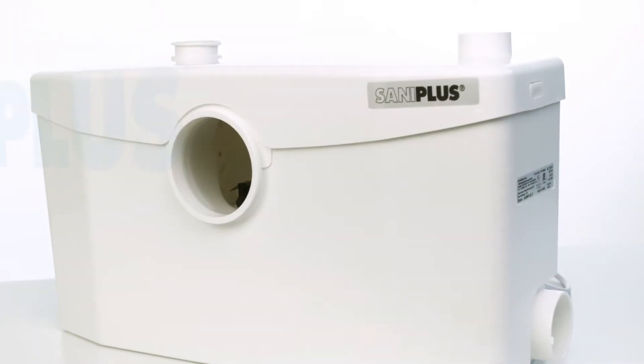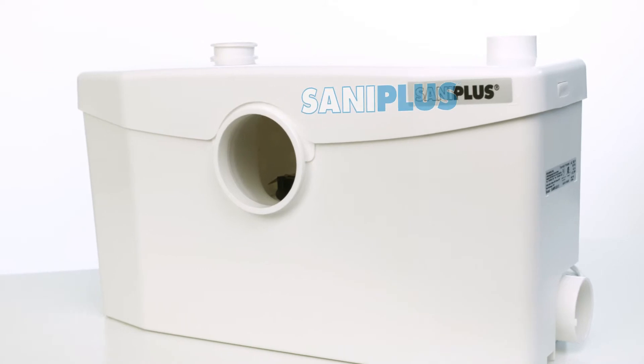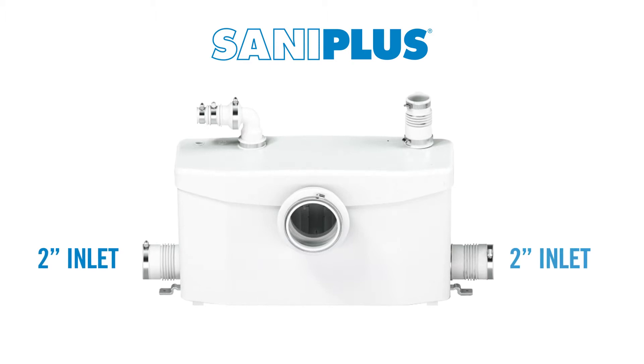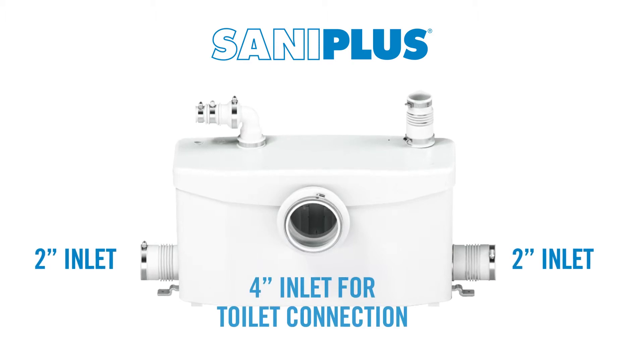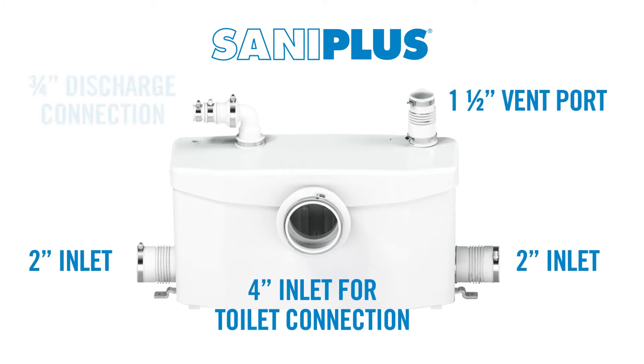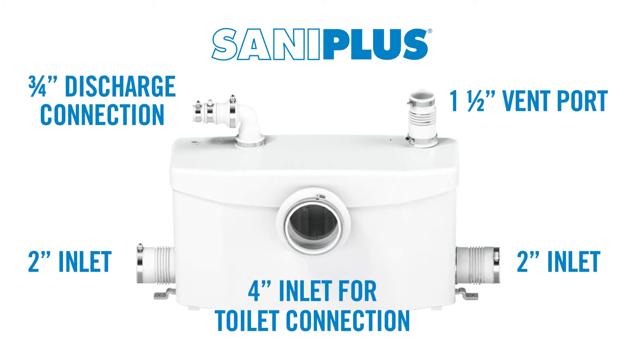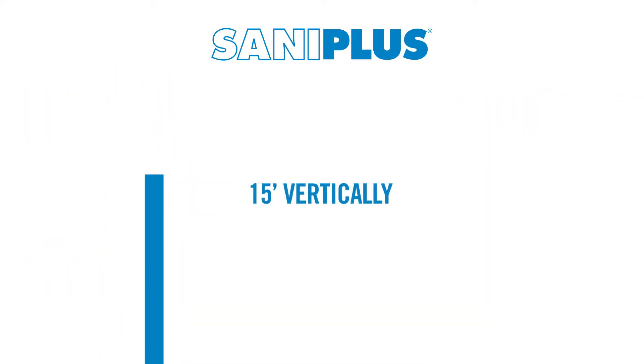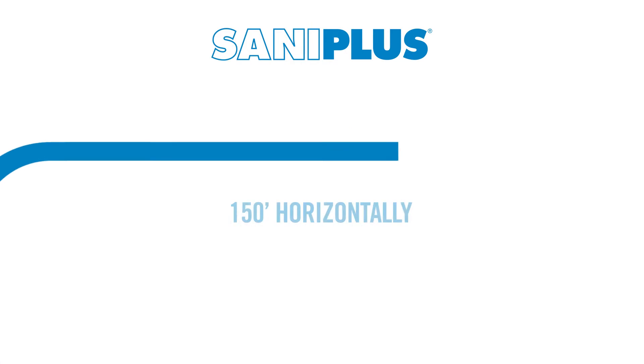One of our most popular macerating units is the SaniPlus. The SaniPlus has multiple inlets and connections that all have their own purpose. The unit has two 2-inch inlets on either side, a 4-inch inlet for toilet connection, and on the top there is a 1.5-inch vent port and a 3/4-inch discharge connection. This powerful system can pump discharge up to 15 feet vertically and/or 150 feet horizontally.